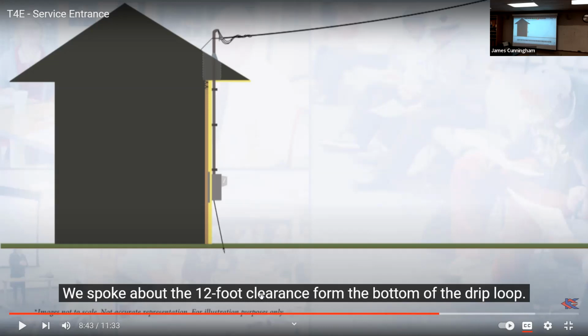So you have to do all those things when you're setting up for an Edison underground service. Also, you're not allowed to have more than 180 degrees in bends. So they're pulling really big wires. Like if you're putting in a new 200 amp service, your wires are going to be big. I showed you what it is. This is for 100 amp service here. Imagine a wire that's 4 times as big as this and having 3 of them for a 200 amp service. The wires are about $12 a foot, at least, and you got 3 of them. So that's why they require this. It makes it easier for them to pull those big heavy wires through for a 200 amp service.